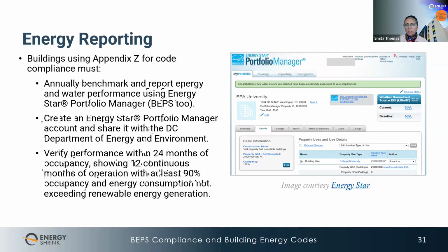This applies if you're producing energy where your equipment does not allow net metering. Net metering is where you're producing energy, and if you're producing excess energy that your building is not using, you're allowed to put it back into the grid. But there can be constraints where you're not allowed to do that—this is a real problem because, for example, the electricity provider in DC has a limit on how much you can put back into the grid, because a surge of electricity coming from a building can upset their distribution system. So they've set limits on it for their own grid reliability.